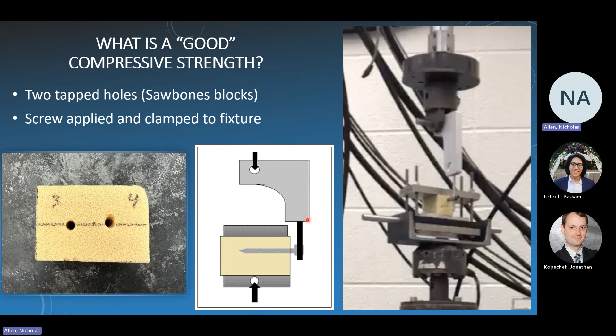That's as we're applying an oscillatory load, right? Every second, applying a load, and we keep on increasing the load and increasing the load, and then monitor the deflection here. This simulates a rod on that pedicle screw that is in this foam block, and then when does it fail, right? If you ask me, oh, are these loads appropriate or was it mimicked on, I would just say, let's talk to Dr. Vore, who's not here. But as a publication, I can share it with you and connect you with him. But either way, it mimics a biological load that keeps on increasing until it fails.